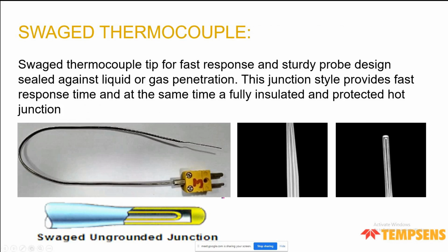Then we also do swaged thermocouples. So these are reduced tip thermocouples. The thermocouple measures its own temperature, so as the mass is smaller at the tip, it will give you a faster response. For example, a 0.25 millimeter thermocouple can have a response of 30 milliseconds. So with the reduction of the tip we get a fast response, and with the higher diameter of the extended portion we get more strength. This is being used in a lot of industries to get faster response and good mechanical strength. We supplied also to GTRE and a lot of customers like IGCAR and VSSC, some of these sensors. We have in-house radiography and other measurement facilities, so they can all be checked and measured in the company.